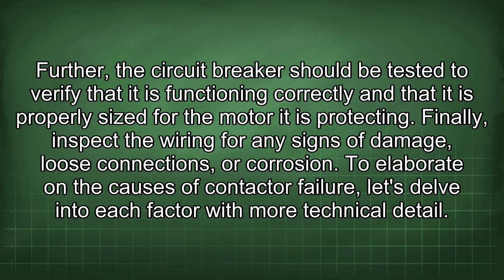Further, the circuit breaker should be tested to verify that it is functioning correctly and that it is properly sized for the motor it is protecting. Finally, inspect the wiring for any signs of damage, loose connections, or corrosion. To elaborate on the causes of contactor failure, let's delve into each factor with more technical detail.